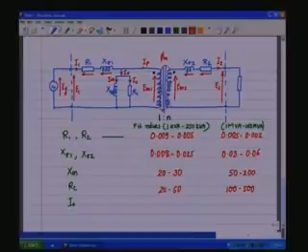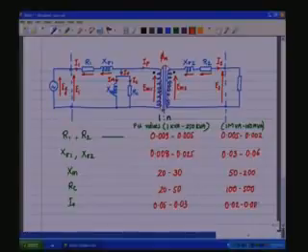The no load current I0 that is drawn from the primary source varies from 0.05 to 0.03 in the 1 to 250 kVA range and 0.02 to 0.005 in the 1 to 100 MVA range. This is a very useful table which you can use for comparing various rating transformers.